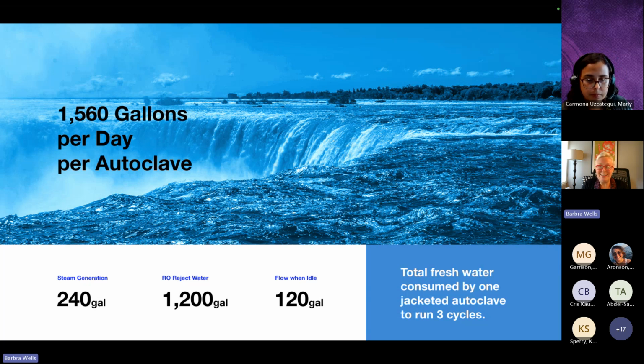So what does this mean? For a typical jacketed autoclave running a vacuum cycle, the RO water use is about 80 gallons. So multiply it by 3 cycles, and we've got that 240 gallons. Now, for every gallon of RO water produced, there's typically 5 gallons or more of reject water. That means those 240 gallons produce 1,200 gallons of reject water that you have to treat before you can dispose of it or reuse it in any way.